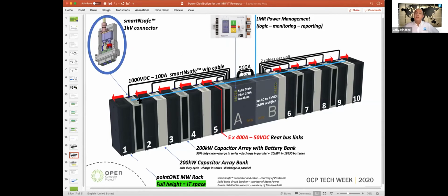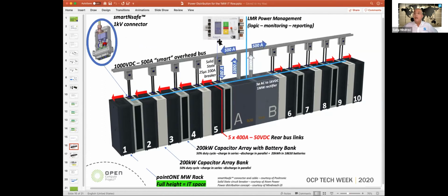But again, the key part of the functionality in such a distribution system is to use a smartNsafe connector that has sensors built in, and also a smart and safe wire that has the ability to detect faults, to detect partial discharge, and react very quickly. In order for such system to react so quickly as needed, it's only feasible with solid state breakers. Conventional breakers simply cannot handle this type of fast reaction that's needed in a system as shown. So just let's look at this in a little bit more detail.